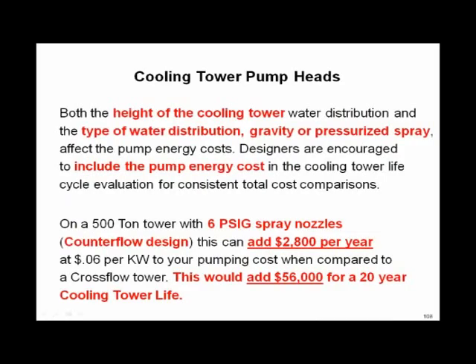So if you look at all this, counterflow versus crossflow, we put this in here to give you a picture of it. There can be a pretty significant operating cost difference between the counterflow and the crossflow if you look at the pump head loss calculation required for the counterflow tower versus the crossflow. The main thing I'm trying to get across to you: don't come up short. ASHRAE says you've got to do a detailed pump head loss calculation. When you do that, account for this to make sure you have the right pump head on your condenser water pump.